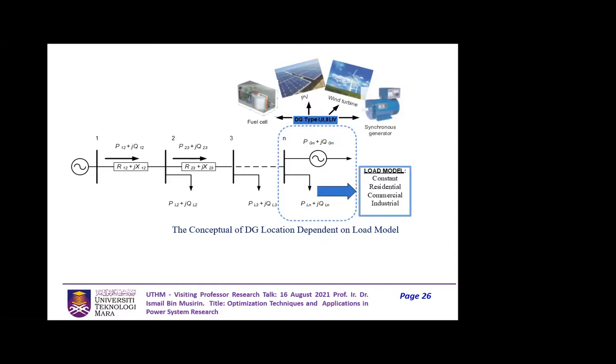But when you talk about overcompensation phenomenon, when you install a capacitor bank, or PV, or wind turbine, the voltage goes up, above 1.05. This is something we don't want, because over voltage supply can also disturb appliances at our residential premises, and so on. This is something that also needs to be avoided.